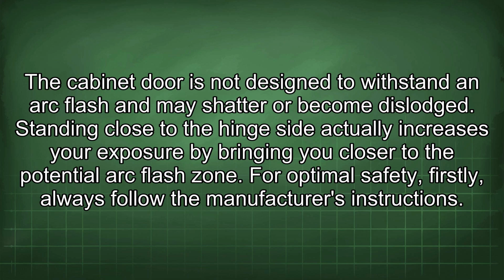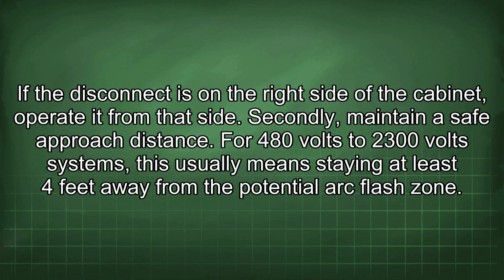For optimal safety, firstly, always follow the manufacturer's instructions. If the disconnect is on the right side of the cabinet, operate it from that side. Secondly, maintain a safe approach distance. For 480 volts to 2300 volt systems, this usually means staying at least 4 feet away from the potential arc flash zone.